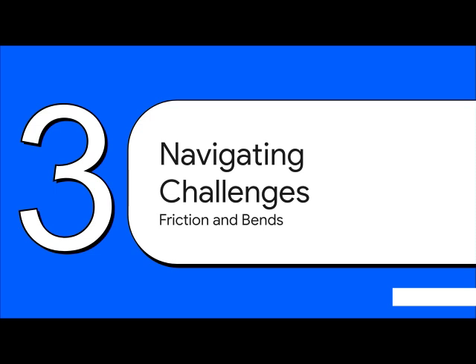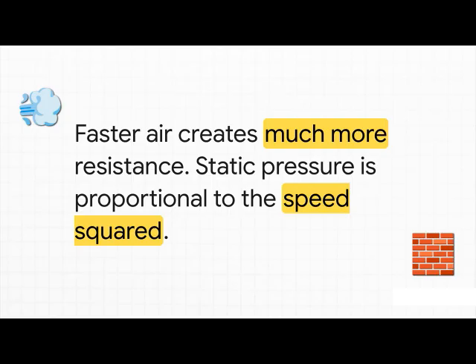It's going to face some challenges, some obstacles that create resistance, and we're going to talk about two big ones: friction and bends. Here's a simple but important rule of physics when it comes to air: the faster you try to shove air through a duct, the more resistance you get. The duct pushes back, and that's what the main fan has to fight against. But how much harder does it have to work? Probably a lot more than you think.